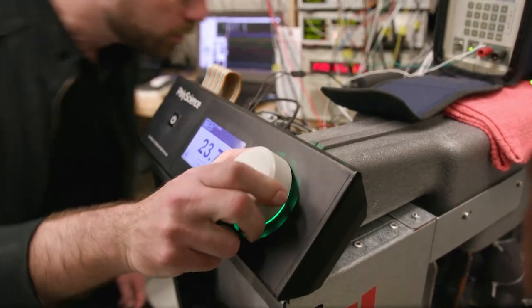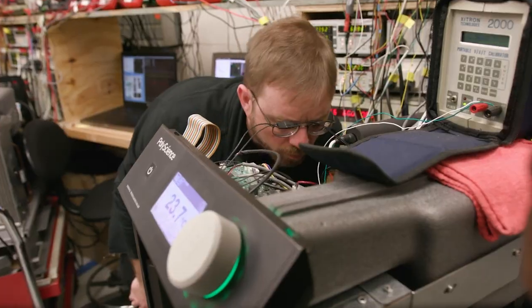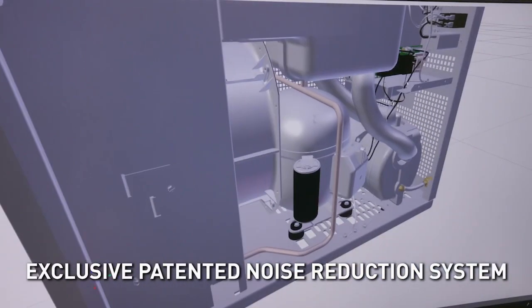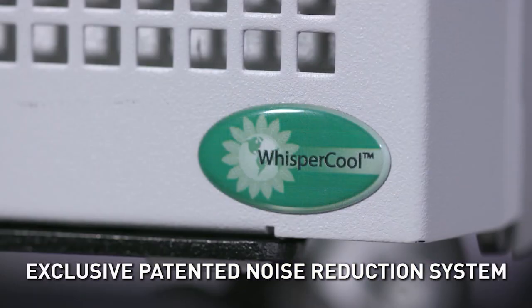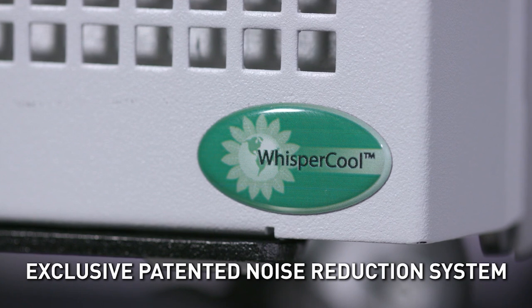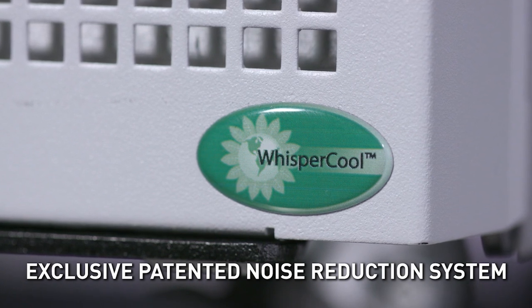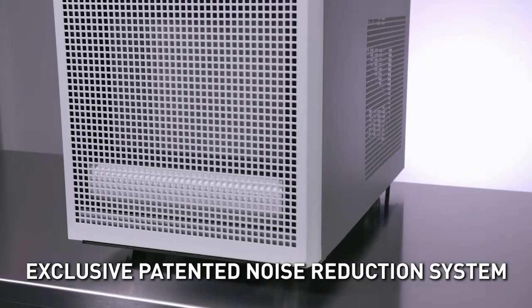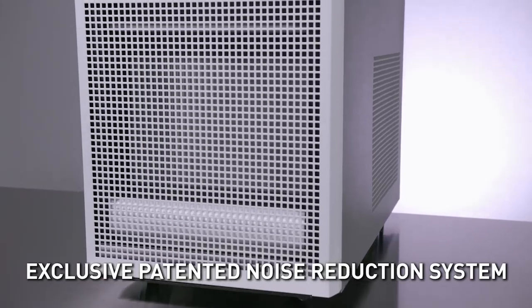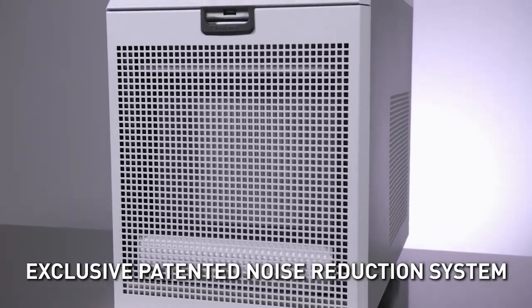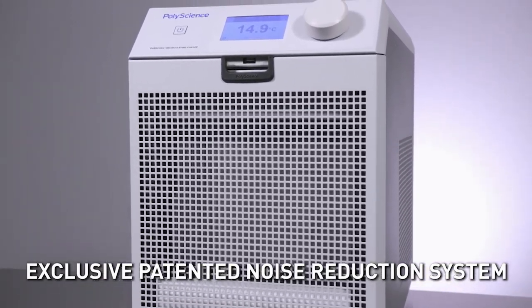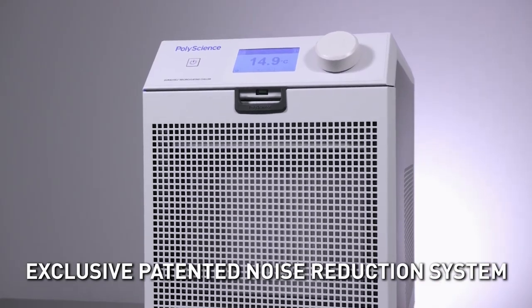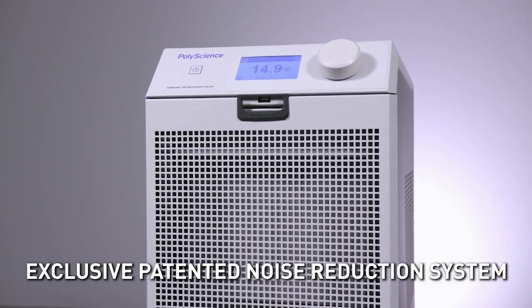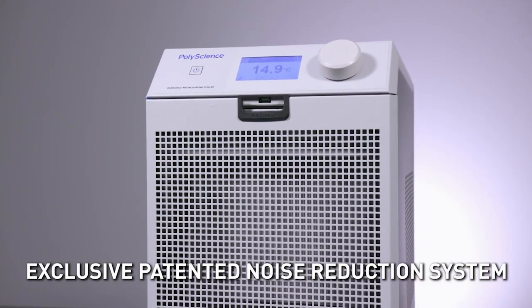These new high-performance chillers utilize our exclusive patented noise reduction system. The WhisperCool system evaluates the demand for cooling from the application, then slows the fan speed to the minimum necessary to maintain control point, making the chiller extremely quiet and maintaining the optimal temperature at the same time.